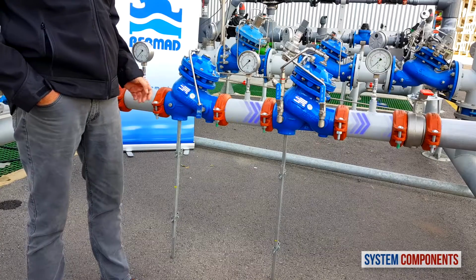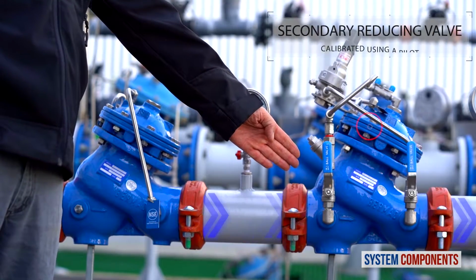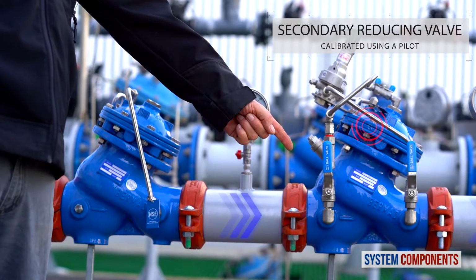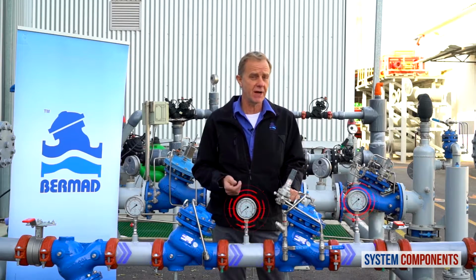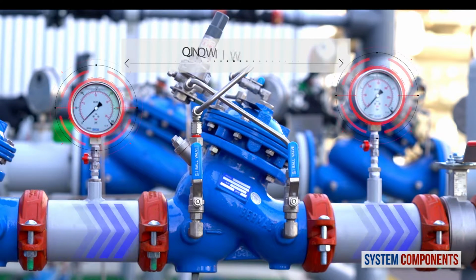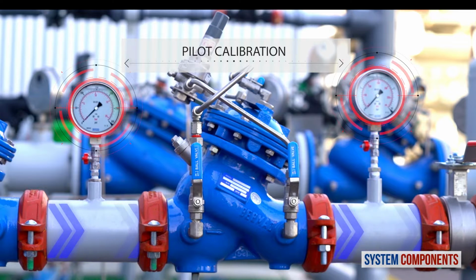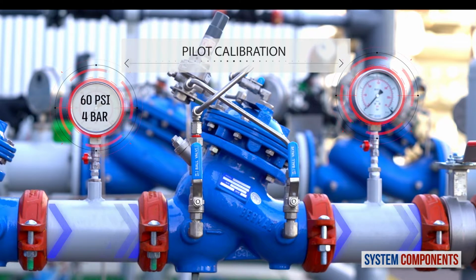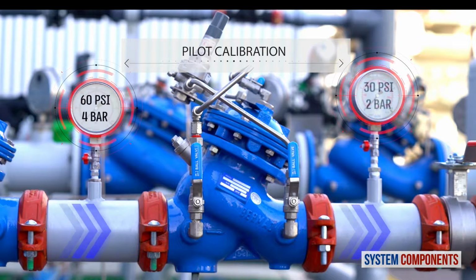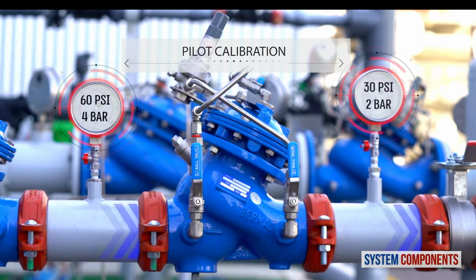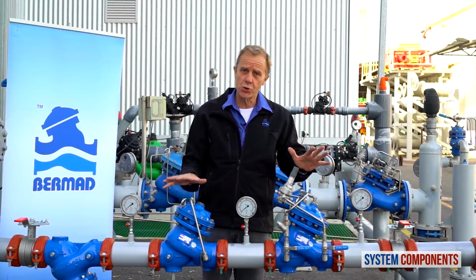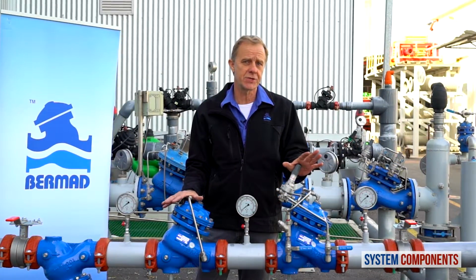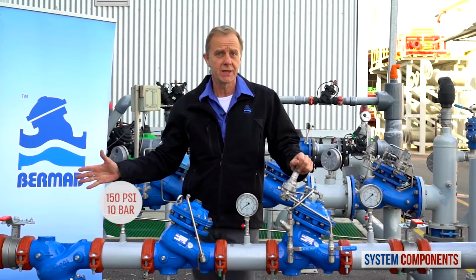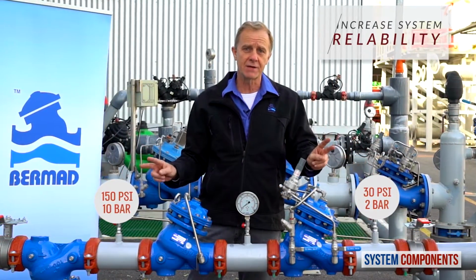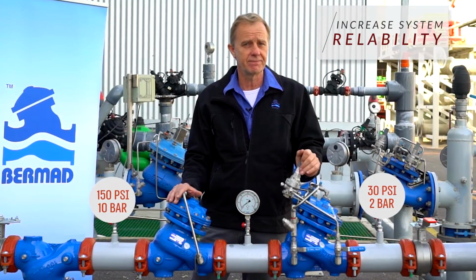The secondary pressure reducing valve is located downstream of the primary reducing valve and can be adjusted, unlike the primary valve. It is used to further reduce the pressure to the exact value required. Referring to the example we mentioned previously, where the inlet pressure will be 10 bar, reduced by the primary proportional reducing valve to 4 bar, we can further reduce the pressure using the secondary reducing valve to any value below 4 bar, let's say 2 bar or 30 psi. So as you can see in this example, by using two pressure reducing valves, we are able to significantly reduce the pressure across the station from 10 bars at the inlet to 2 bars at the outlet, dividing the load with two valves and thereby increasing reliability and service lifetime.